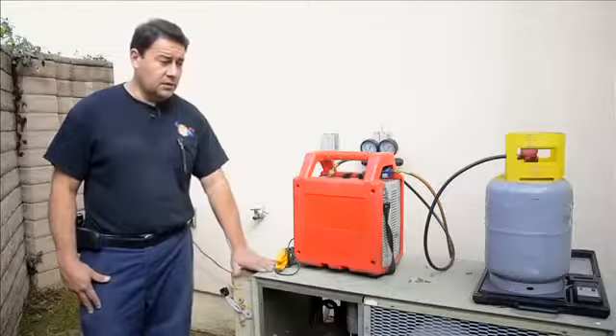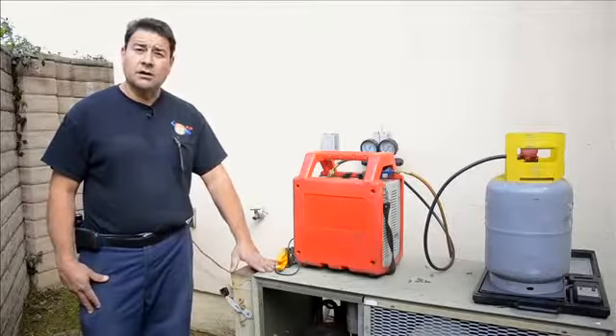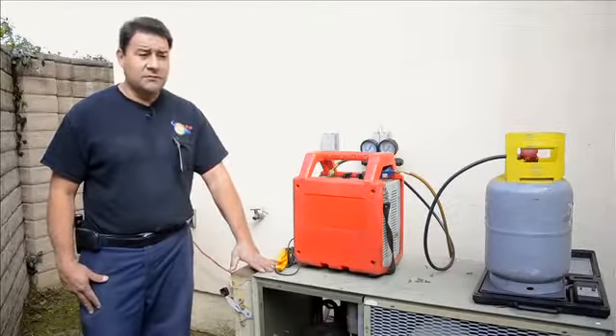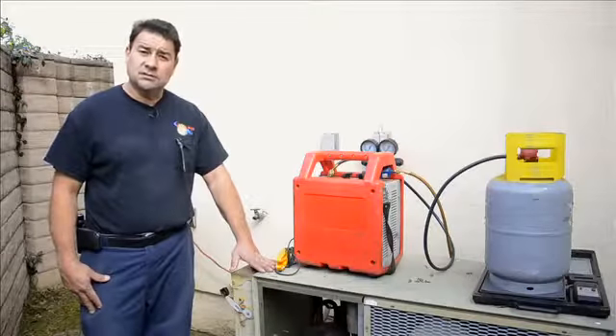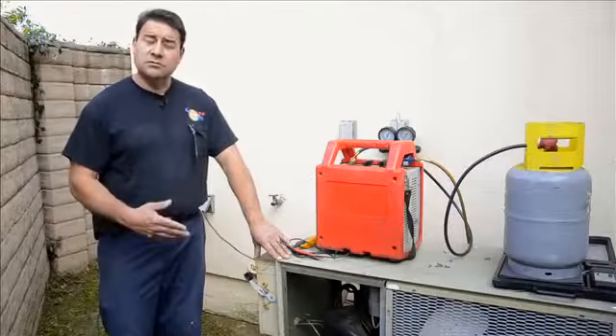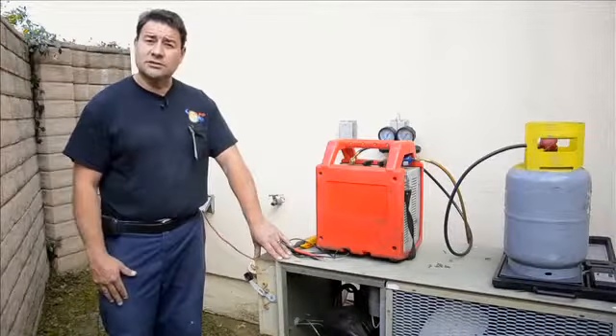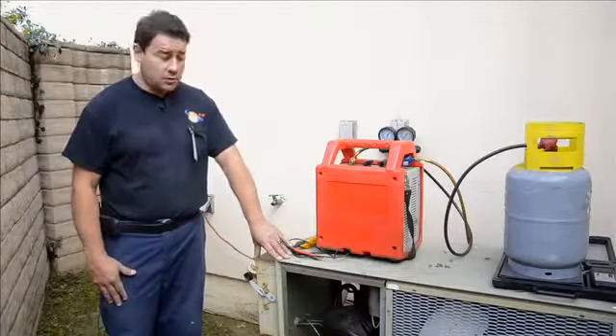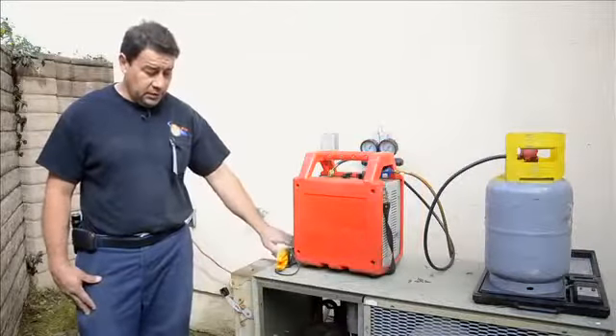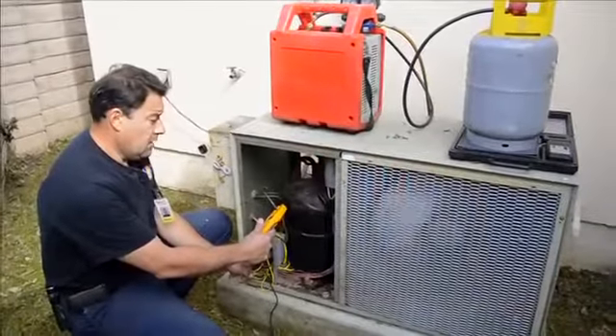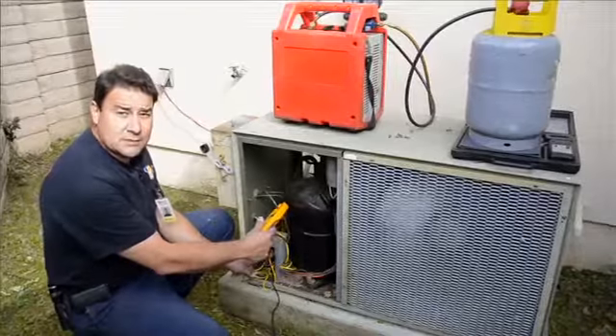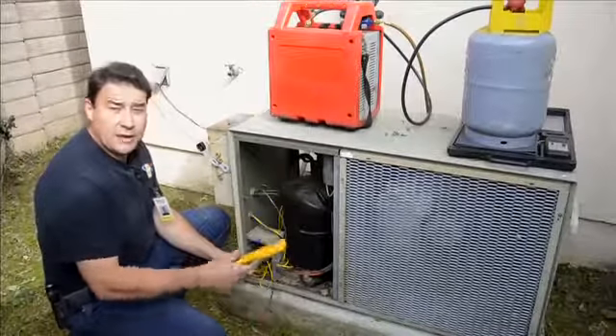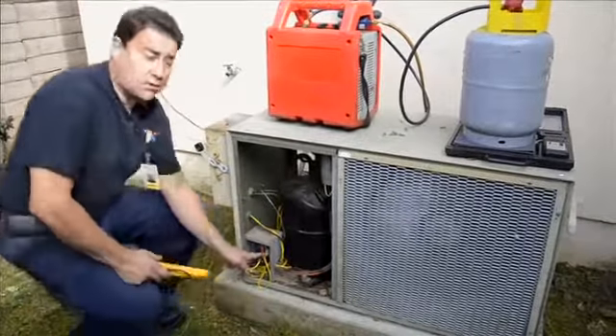This is old equipment. It's manufactured by Heil. 1983 is when it was manufactured, and it's 8.6 SEER, seasonal energy efficiency ratio. The customer wanted to remove it because it was very inefficient and wasn't cooling properly anymore. This unit was pulling 18.9 amps, and we'll compare that to the new unit when it's installed.